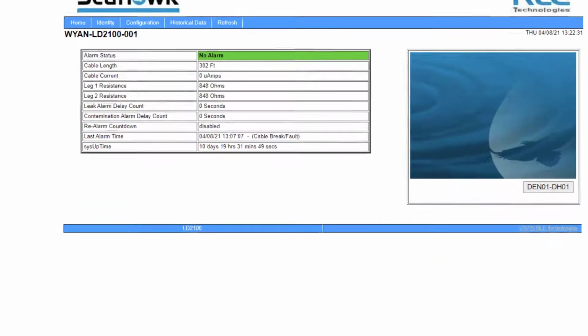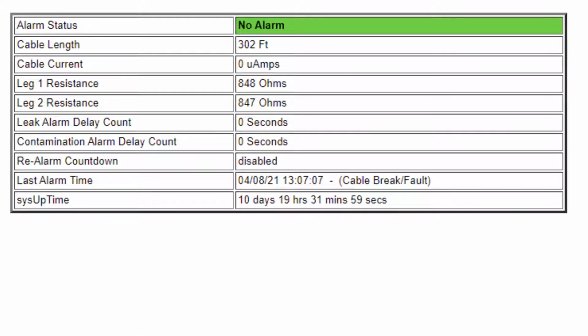So when you look at the controller interfaces, you always want to see that your leg 1, leg 2 resistance is relatively close. If you notice that there's a big variation between leg 1 and leg 2, there might be oxidation or something with one of the connections along that path. RLE does a very good job keeping a tight tolerance on the ohms per foot when they manufacture the cable. But if you have a 7-year-old system out there and you've installed new cable versus what's been sitting under the floor for years, you might get a little bit of a variation. So that's where the calibration comes in handy.